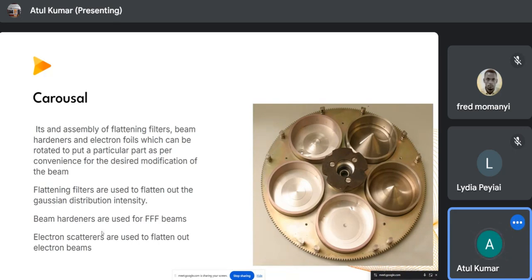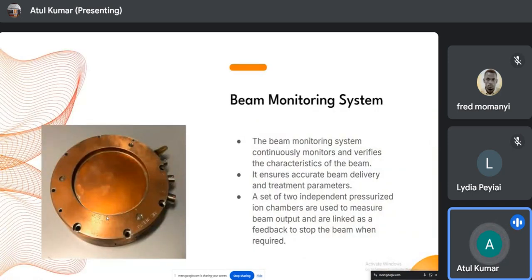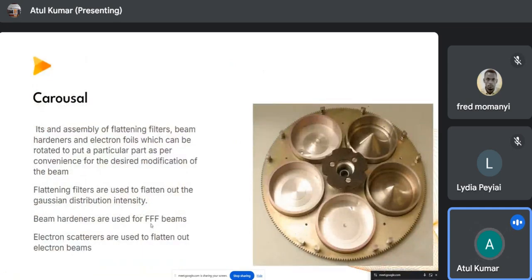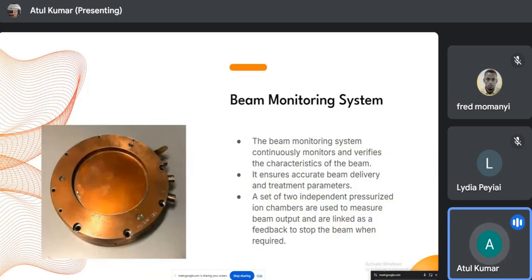Before that, you have something called the beam monitoring system also. This is an ion chamber, a cylindrical ion chamber. Inside it, it is cut in half, and these are two separate ion chambers. You can see one is this, the other one is this one here. These two ion chambers run independently from one another, and they monitor how much X-ray is delivered, so you make sure that you do not give extra dose. There are two devices independent from one another, so that if one fails, the other one can give feedback. Those two run in parallel, and you see whatever MUs you have planned for the patient.